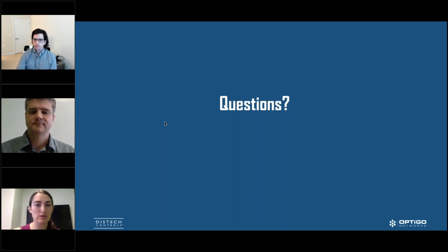But the last question I want to leave with is, BACnet IP panels don't resolve by name, correct? Is DNS something that's needed for BACnet IP devices? There's a lot of people out here on BACnet IP. No. Right now, if you're doing a BACnet job, with the way things typically are in the industry, you're probably going to just ignore host names. You're going to need to use IP addresses specifically.